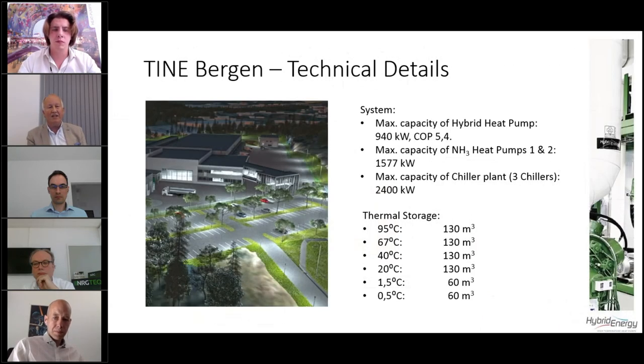If you look at some technical details, the max capacity of the hybrid heat pump is 940 kilowatts with a planned COP of 5.4. The max capacity of the ammonia heat pumps, two of them, is 1577 kilowatts. And max capacity of the chiller plants, including three chillers, is 2400 kilowatts. The thermal storage, as I mentioned, you see there are four storage tanks of 130 cubic meters, and then there are two on the cold side, 60 cubic meters.